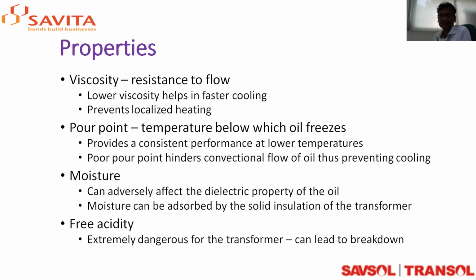Now we'll turn to moisture. Everybody says the mineral oil moisture limit is something around 30, 35, or 40 ppm, not more than that, because of the low moisture saturation point of mineral oil.